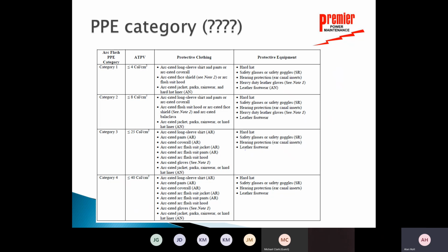Then they have the chart that talks about requirements for protective clothing. You can still see they're using the outdated chart for category clothing. That's not acceptable anymore to use this chart if you've got the incident energy written on the label, which means that you've actually done an arc flash analysis. So I want us to get away from this chart.